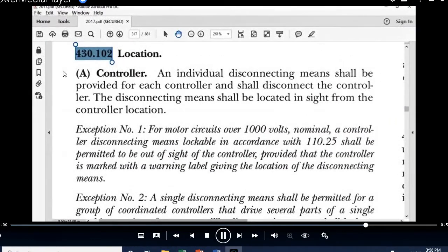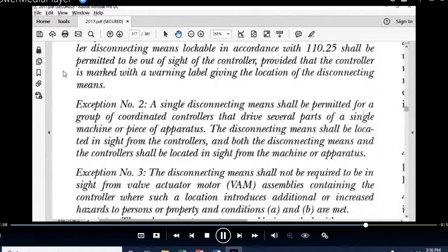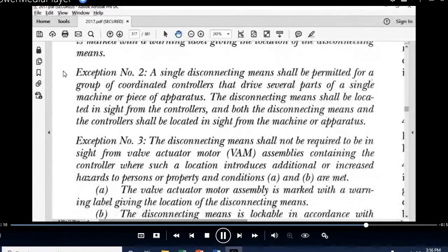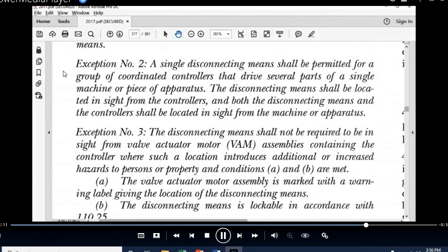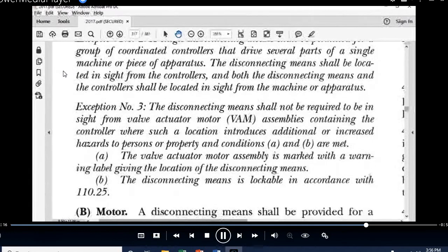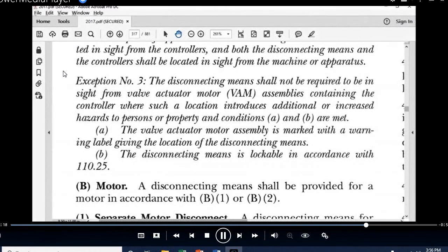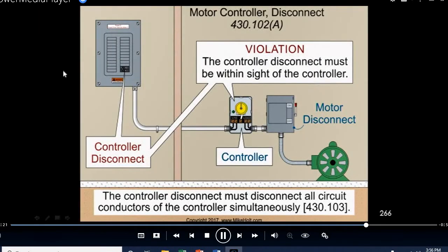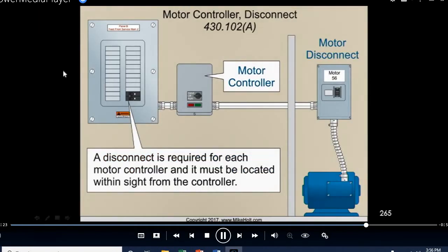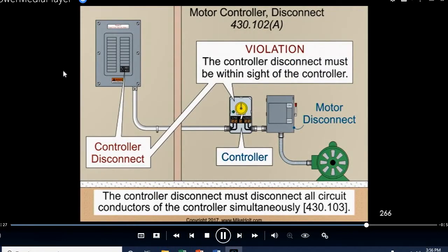An individual disconnecting means shall be provided for each controller and shall disconnect the controller. The disconnecting means shall be located within sight from the controller. Usually your starter is right there at the MCC, so it's a disconnect. Then in the field, when you go like in another room, you have to have the disconnect within sight of the controller, and there is no exception. That would be a violation.